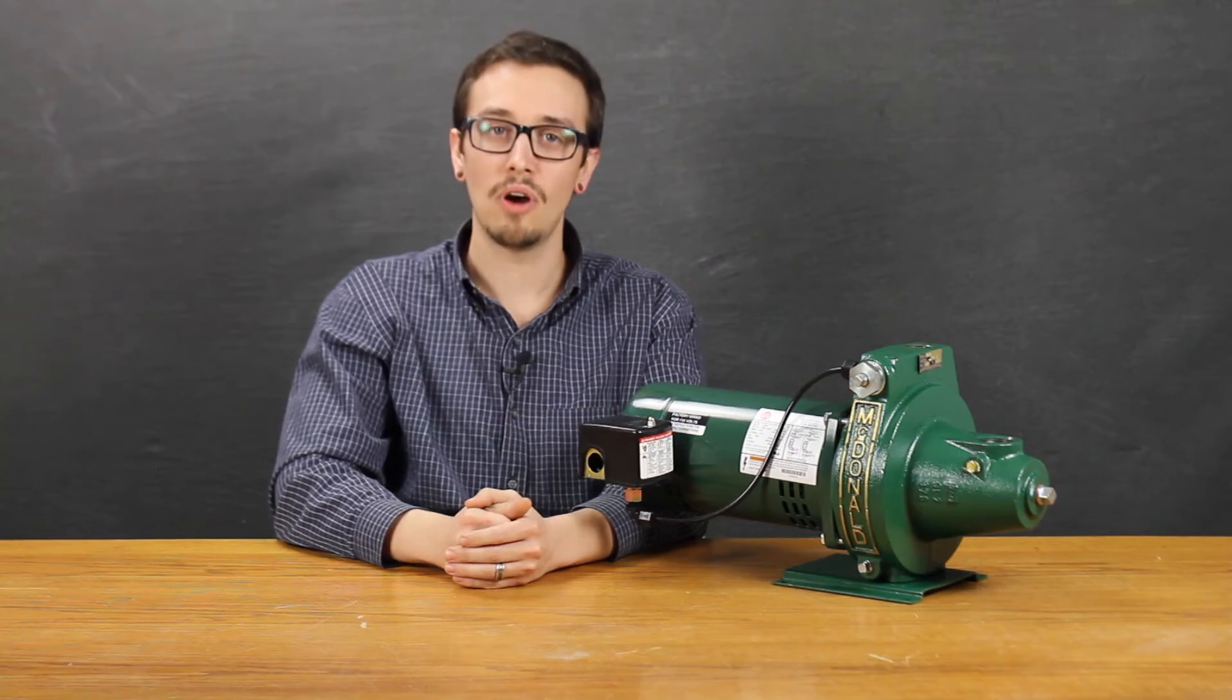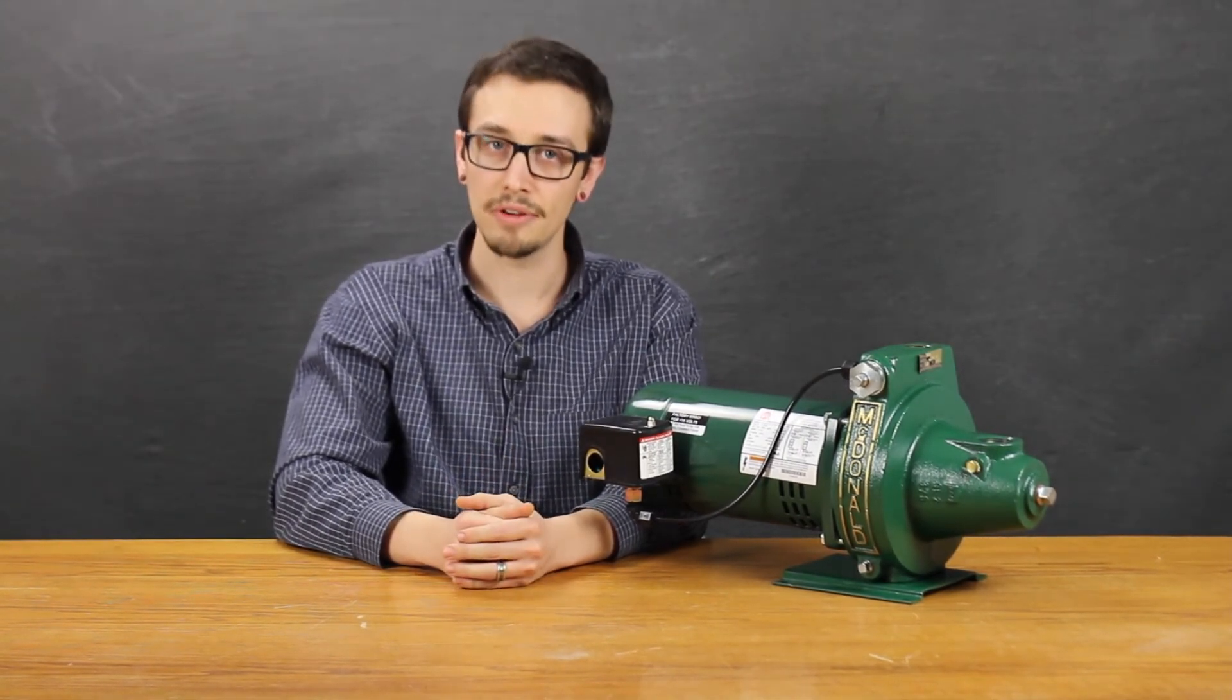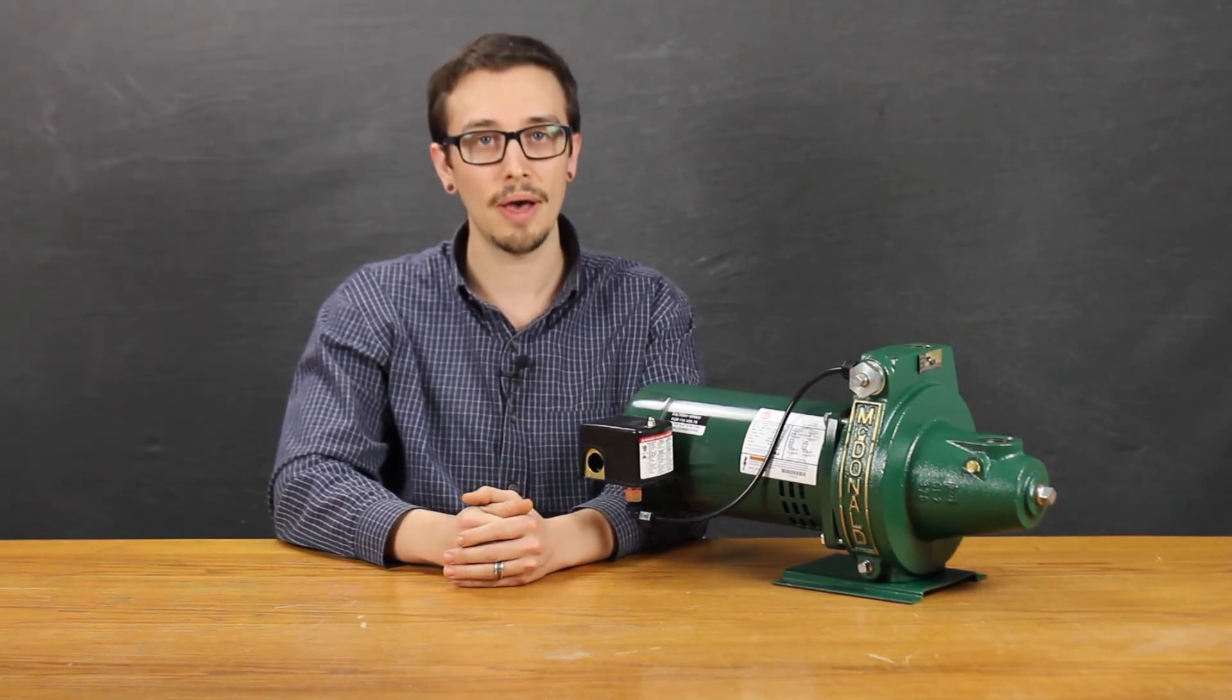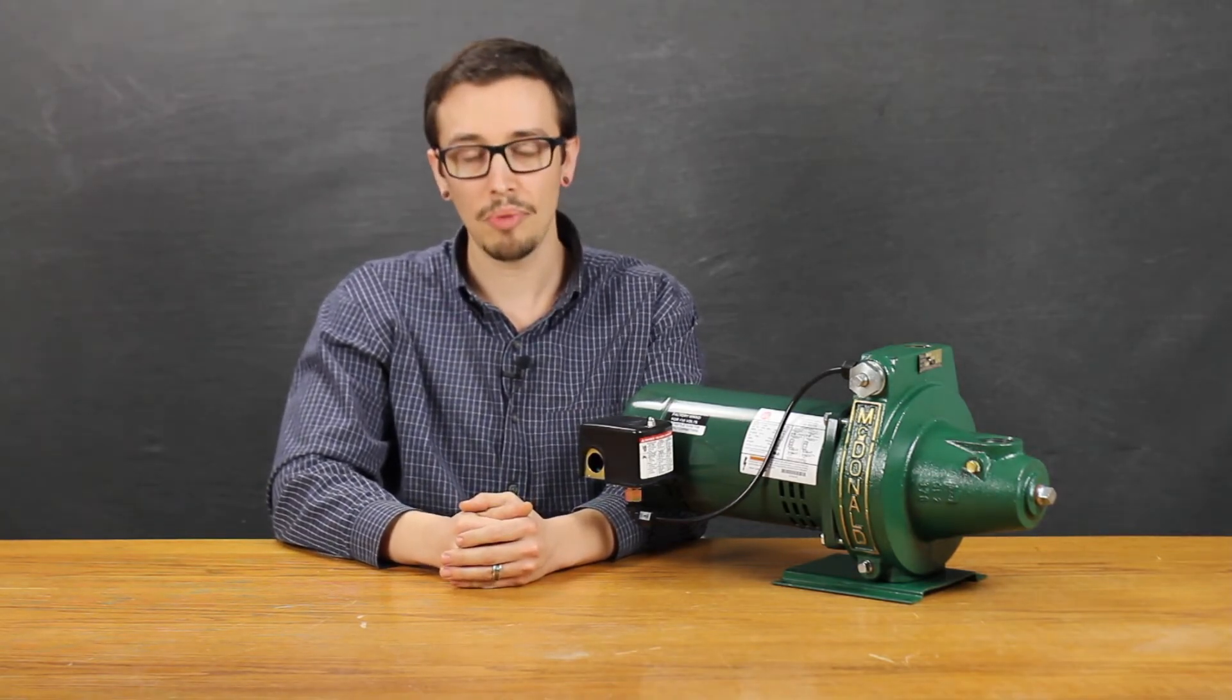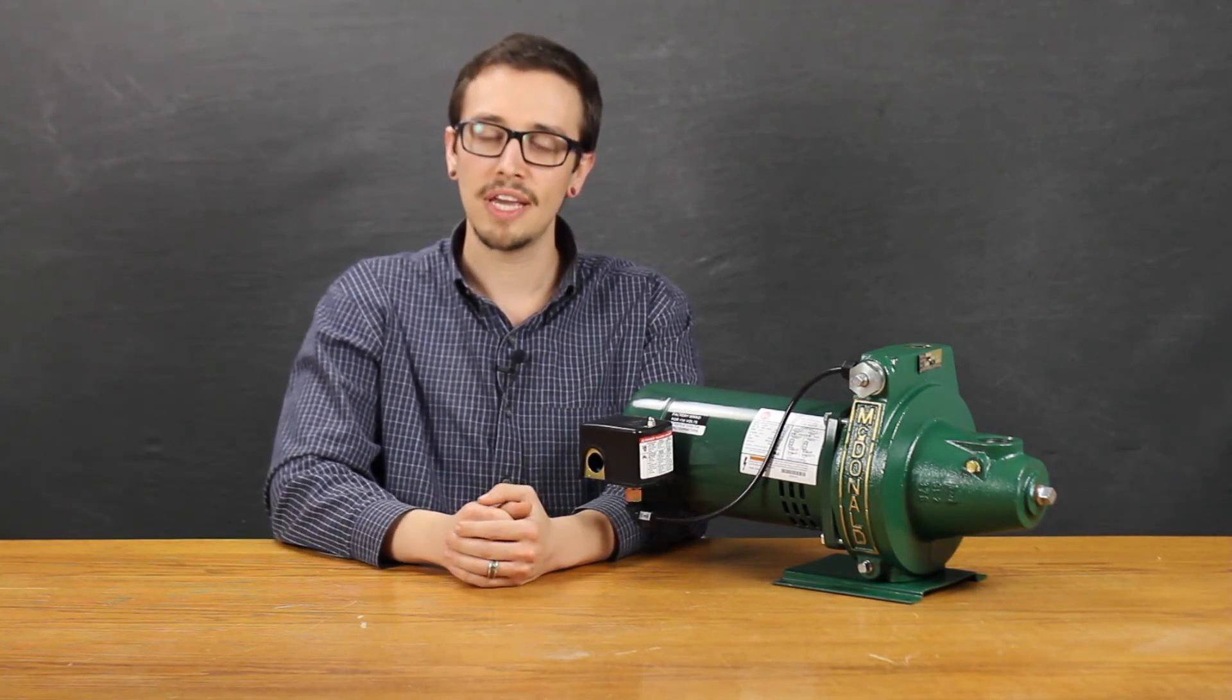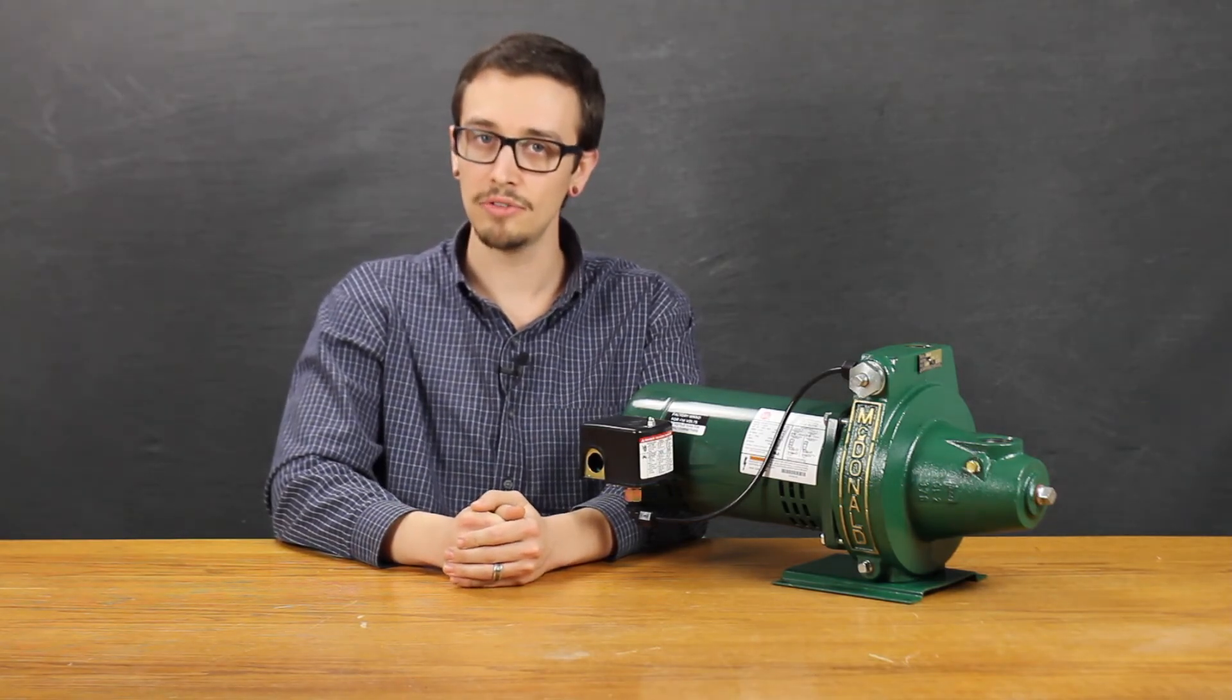The motors on all of these pumps are single phase open drip proof type motors or ODP as they're commonly referred to and run at a constant 3500 rpm. They come standard in a dual voltage configuration, meaning that you can easily switch the pump from 115 to 230 volt. The motor of this pump comes with ball bearings and a standard 5/8 inch ceramic carbon rotating mechanical seal.